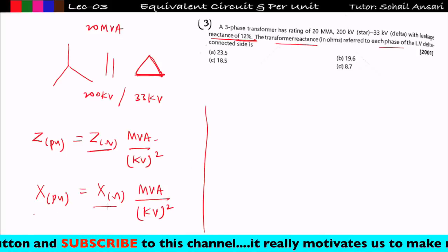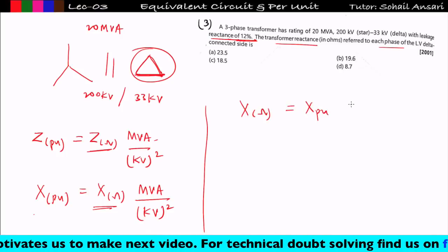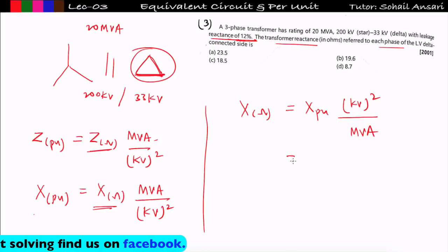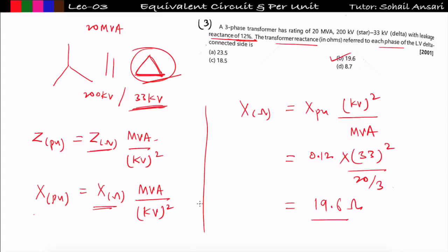For the delta (LV) side, line voltage equals phase voltage = 33 kV. X in ohm = X_per_unit × (V_phase)² / (MVA_per_phase) = 0.12 × (33,000)² / (20/3 × 10⁶) = 19.6 Ω. Option B is correct.